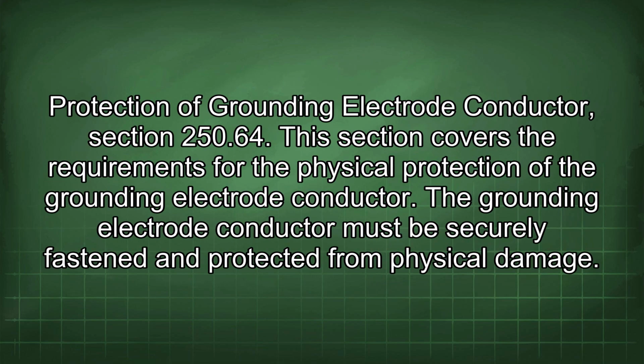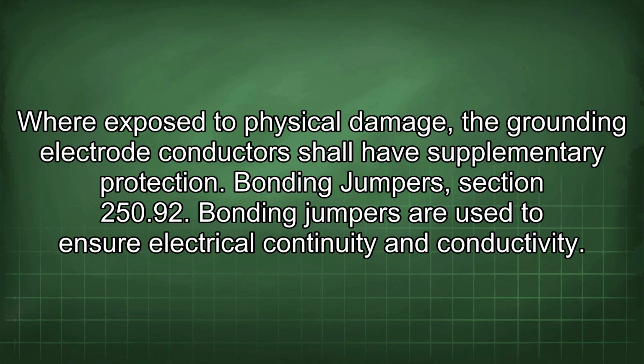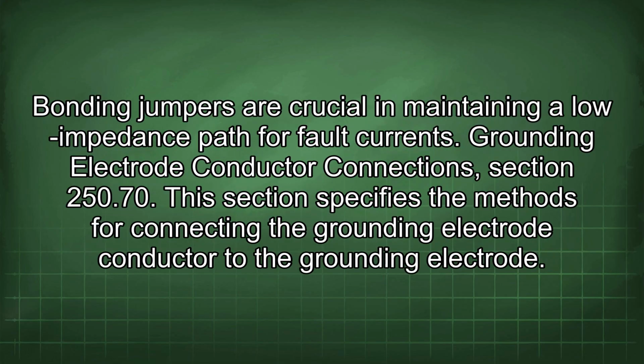Protection of grounding electrode conductor, section 250.64. This section covers the requirements for the physical protection of the grounding electrode conductor. The grounding electrode conductor must be securely fastened and protected from physical damage. Where exposed to physical damage, the grounding electrode conductors shall have supplementary protection. Bonding jumpers, section 250.92. Bonding jumpers are used to ensure electrical continuity and conductivity. Bonding jumpers are crucial in maintaining a low impedance path for fault currents.